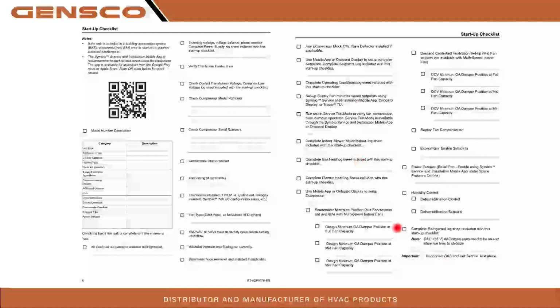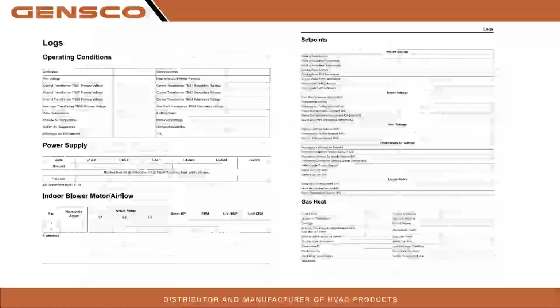We do recommend doing startups on everything. So many times we get a call in two years saying something has failed, and I ask for a startup, and there's no record of a startup, but we don't know the exact startup date because nothing got registered, or nobody ever gauged up to the system, and it hasn't had maintenance in a couple of years too. So there's a lot of reasons to complete the startup.